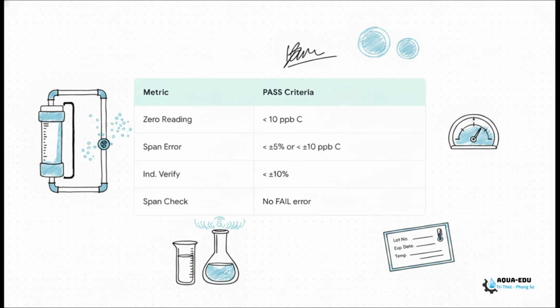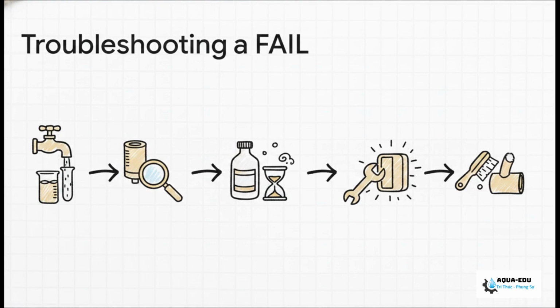Make sure you write all this down in blue ink, capturing your lot numbers, expiration dates, sample temperatures, and your signature. Now, if those readings drift or you get hit with a fail stamp, follow this exact troubleshooting hierarchy. First, rinse the system with 0 water for multiple blank cycles. Second, check or just replace the CO2 scrubber. Third, verify your acid and oxidant haven't expired or gotten contaminated somehow. If that zero drift is still running high, it's time to request professional NDIR or UV maintenance. And finally, check the reactor and sparger for any organic coating or scale.